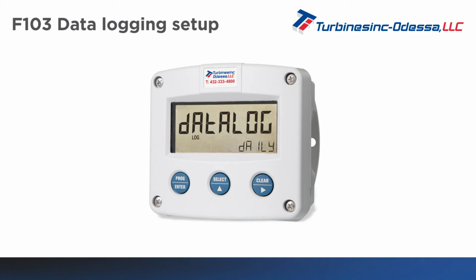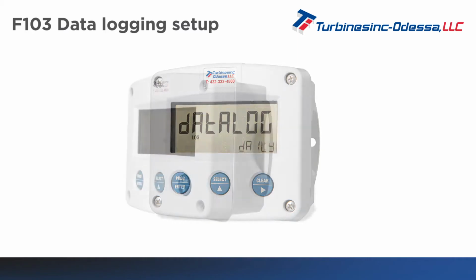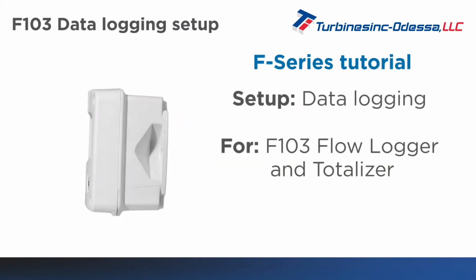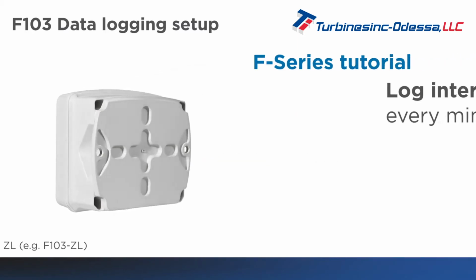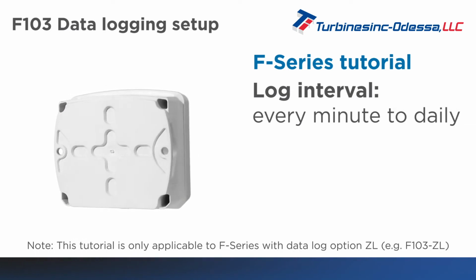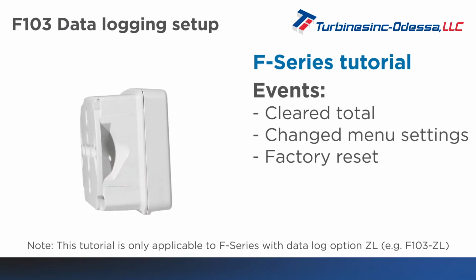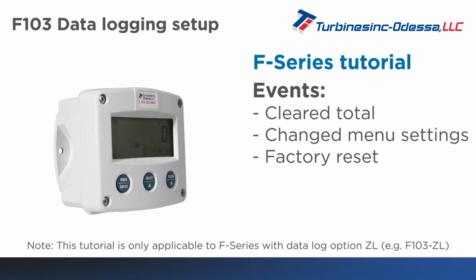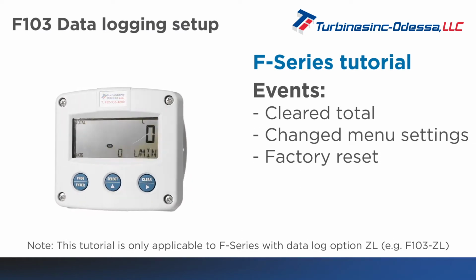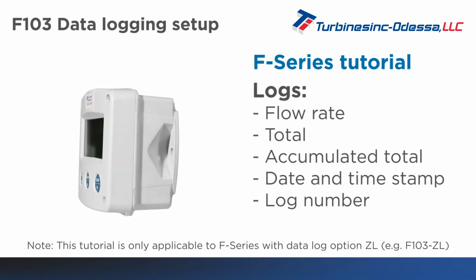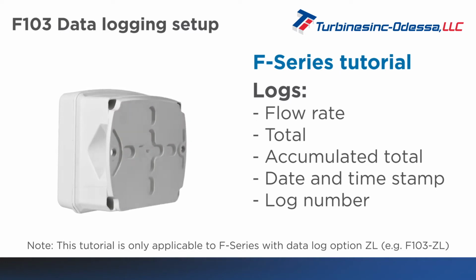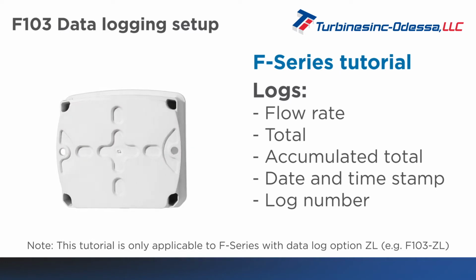When you need to easily monitor your flow measurements and historical data events over time, the logging feature on the F103 is the perfect tool for you. The log interval can be user-defined from every minute to daily. Events such as cleared total, changed menu settings, or factory reset can also be logged. Each log contains flow rate, total, accumulated total, date and timestamp, and log number.